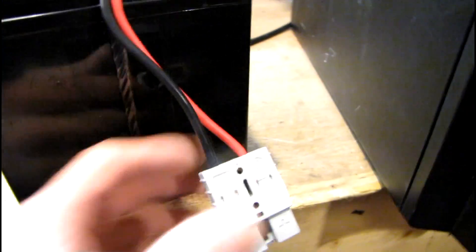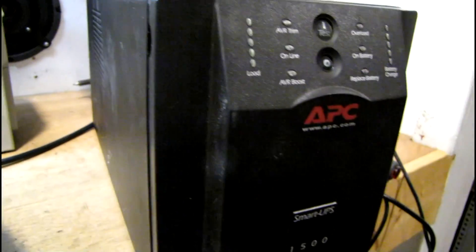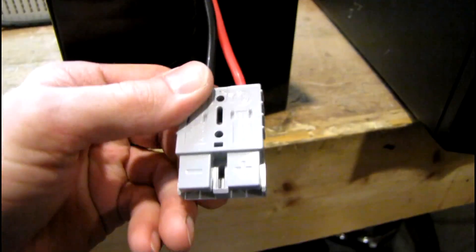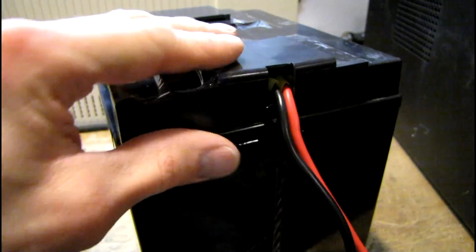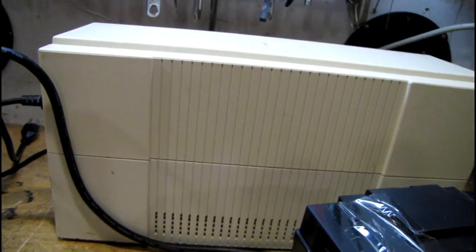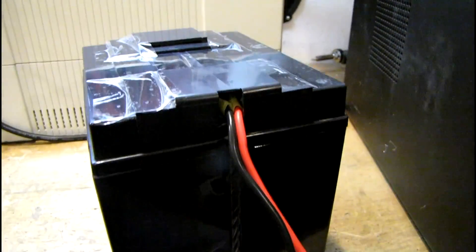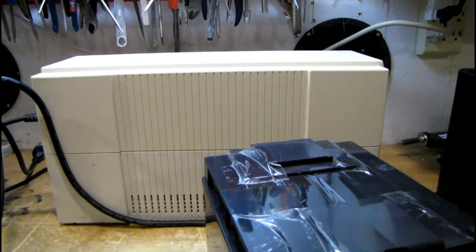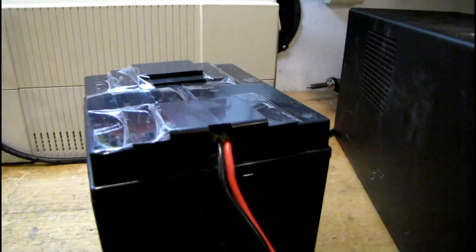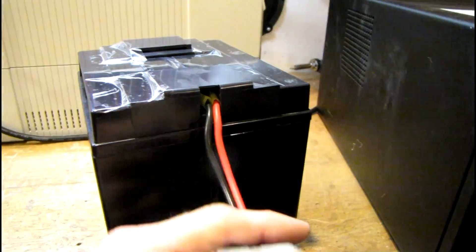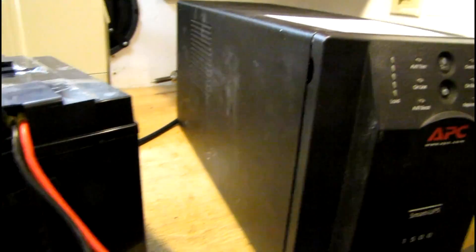It's the first time I've actually put the batteries in one of these newer ones that have user replaceable batteries with the harness and the covers and stuff. These older ones you got to take them all apart and unbolt the cables directly off the circuit board. There's no harness like this. And there's also no safety disconnect in the back like these newer ones have.